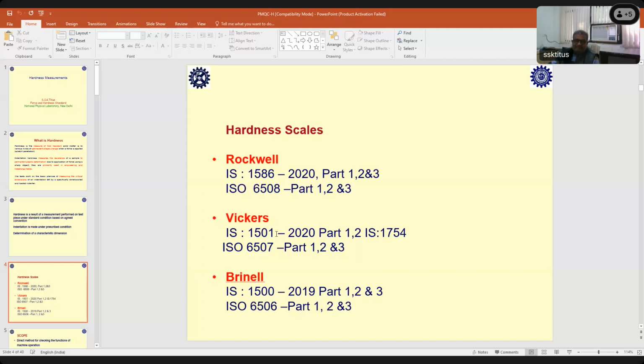Indian standard has adopted the same ISO standard as it is in most cases. As I told you, all these standards have three parts. Part 1 always talks about the general principle, how the hardness test has to be performed. It talks about what kind of indenters, what kind of sharp object, one has to use for making the penetration, and what the different scales available are. Part 2 of the standard generally talks about the testing machines for hardness measurement. There are several testing machines used by calibration laboratories and industries. How these testing machines have to be calibrated, and what permissible tolerance one can have for measuring the hardness, is covered in part 2.